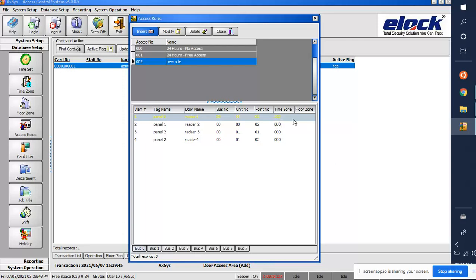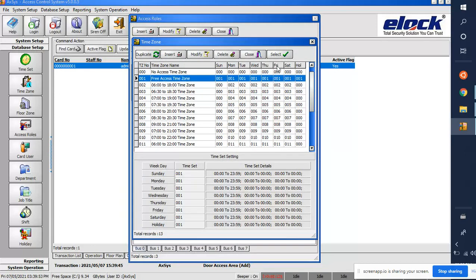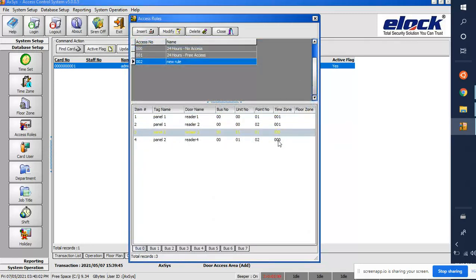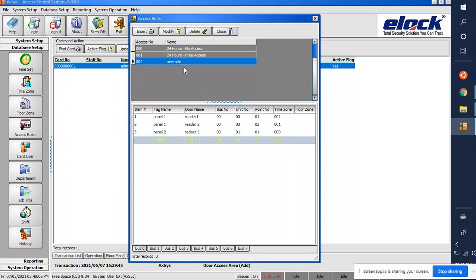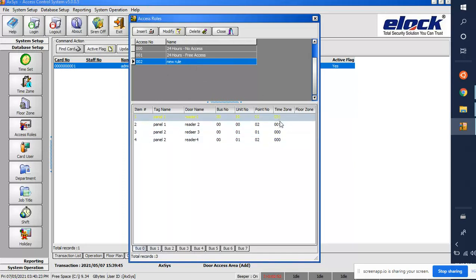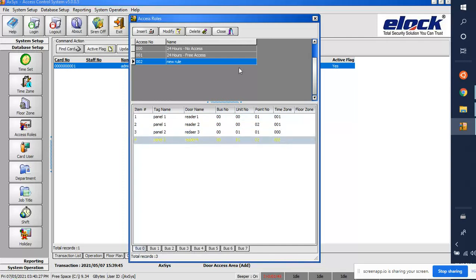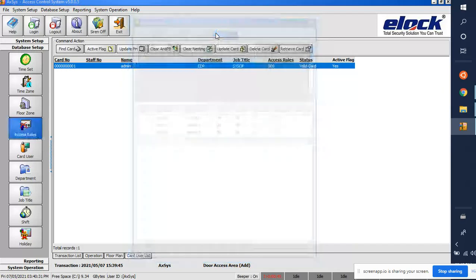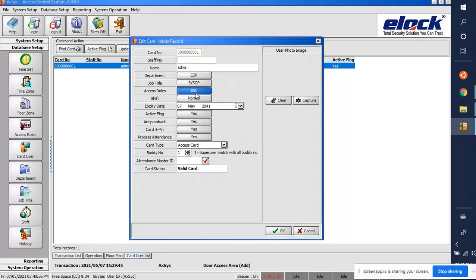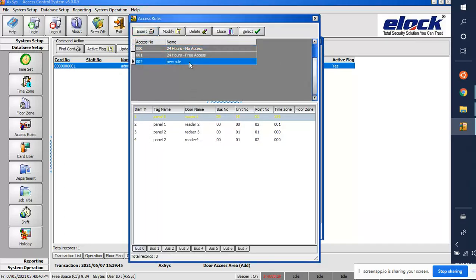In the new rule (002), set Reader 1 and Reader 2 of Panel 1 to full access (time zone 1). Set Reader 3 and Reader 4 of Panel 2 to 0 — meaning no access. So in this new rule, only Panel 1's Reader 1 and Reader 2 will work; Reader 3 and Reader 4 will not. Close this window, go to the user, and set their access role to 'New Rule' (002).